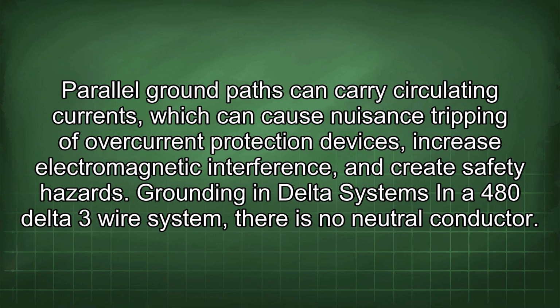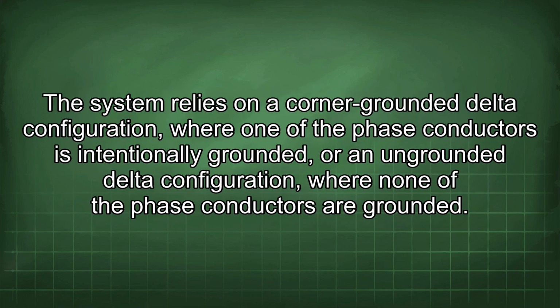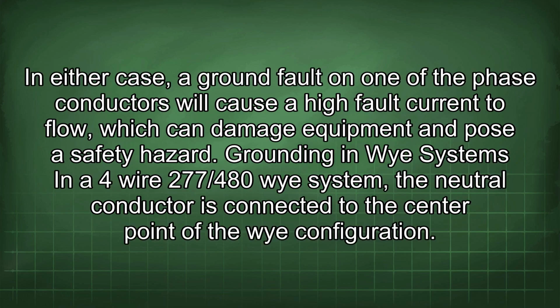Grounding in delta systems. In a 480 delta 3-wire system, there is no neutral conductor. The system relies on a corner-grounded delta configuration, where one of the phase conductors is intentionally grounded, or an ungrounded delta configuration, where none of the phase conductors are grounded. In either case, a ground fault on one of the phase conductors will cause a high fault current to flow, which can damage equipment and pose a safety hazard.